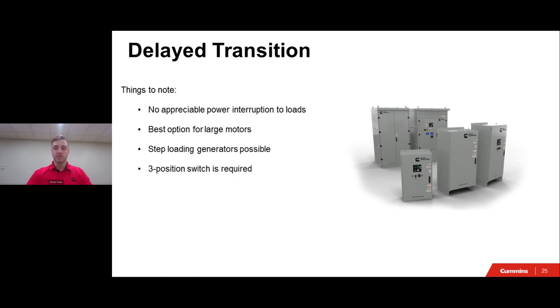So, like I said, back in that slide in the middle piece, imagine you have that normal and emergency source. Your normal source goes away. However, you have those large motor loads on the other end of your transfer switch, so it opens to both sources, and that center off position has that time delay. And then once that time delay is up, it will switch from the center off to the emergency power source.